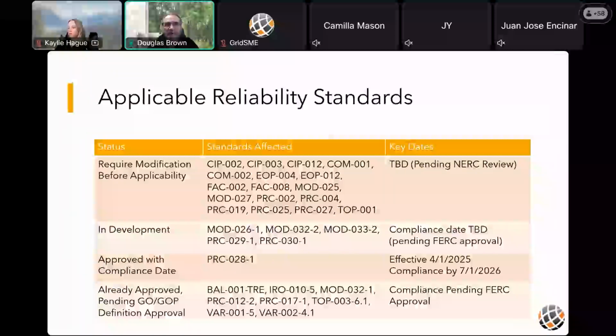In the slide, the mod standards in the first row require modification for applicability. The reason is the language is all very specific to the bulk electric system, and NERC's rules of procedure define the bulk electric system as 100 kV and above. These plants connect to the bulk electric system below that, so the language in each standard has to be modified to make clear they're applicable to plants that had to register under Category 2.